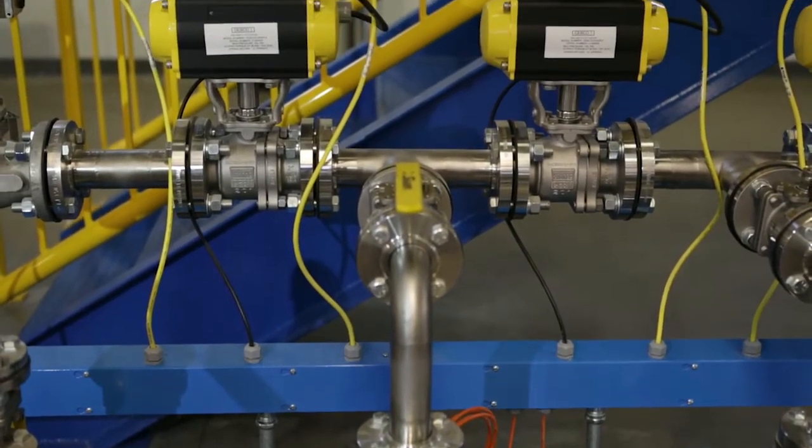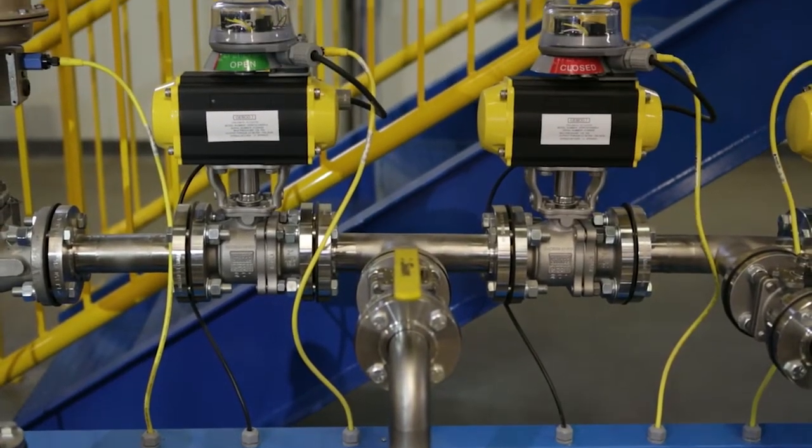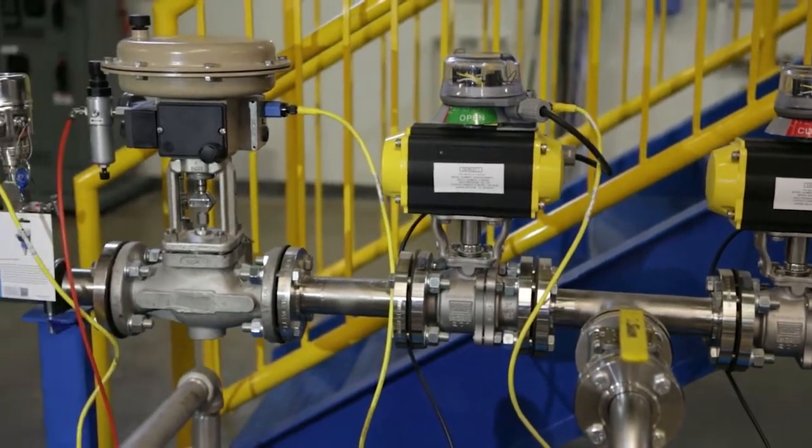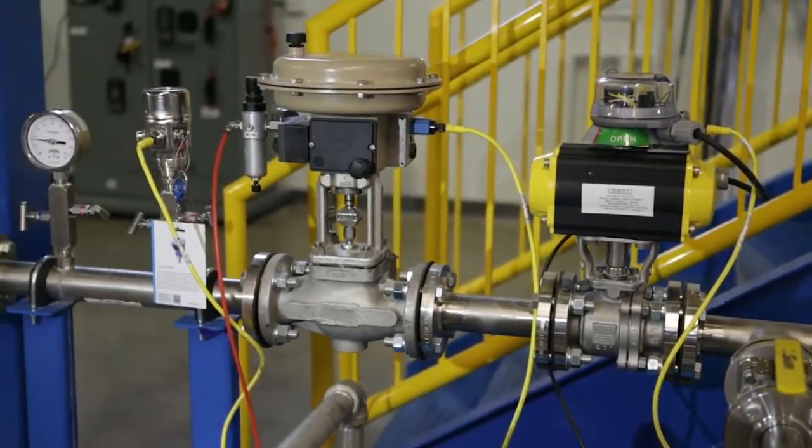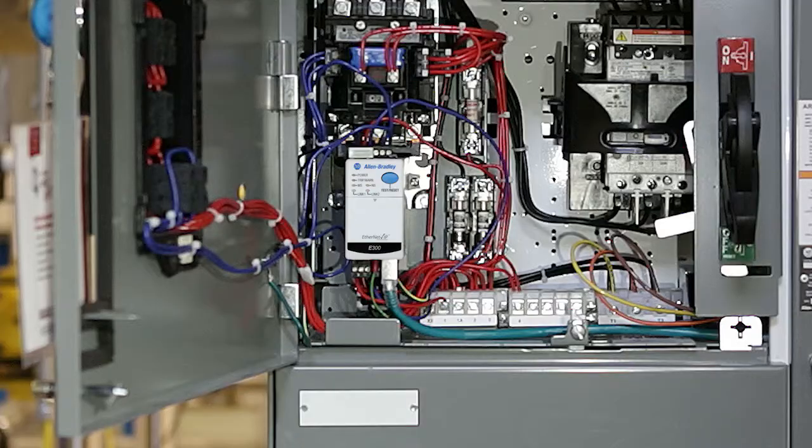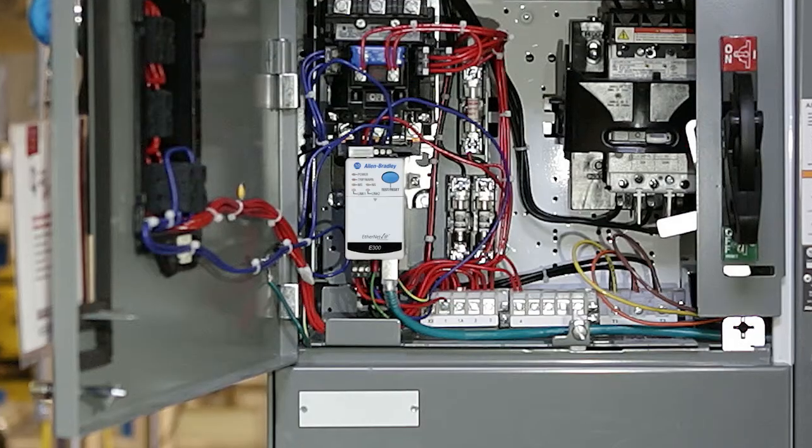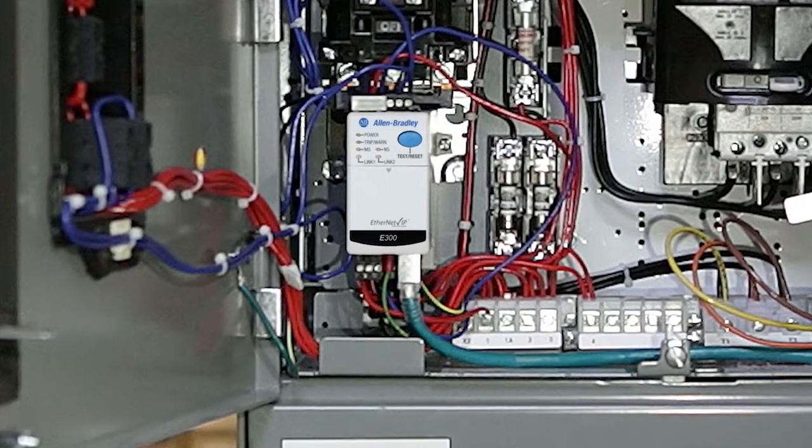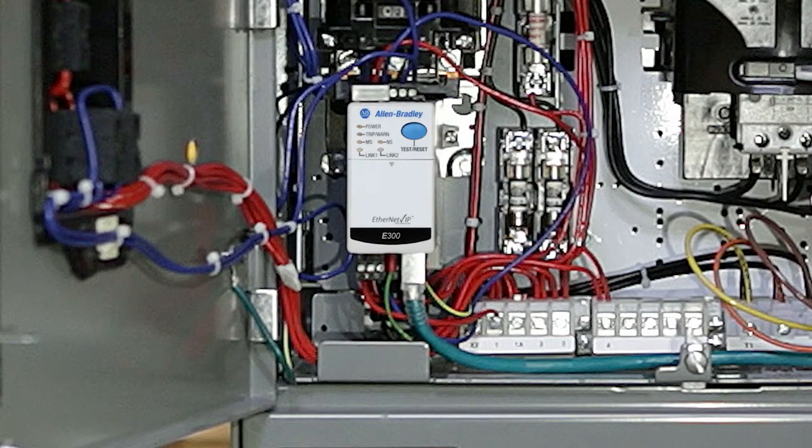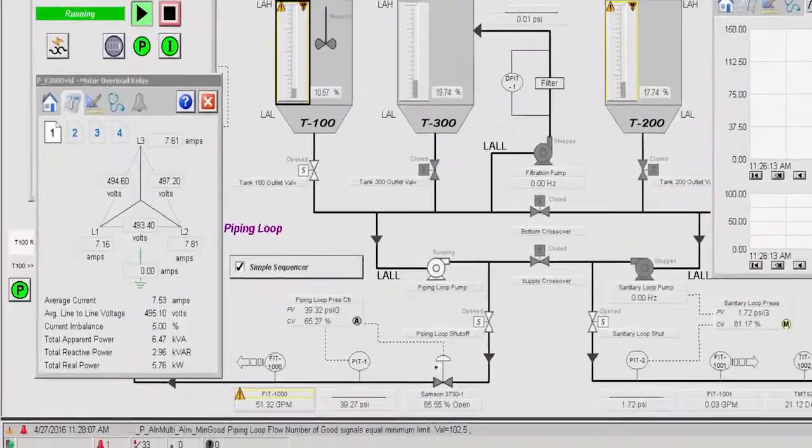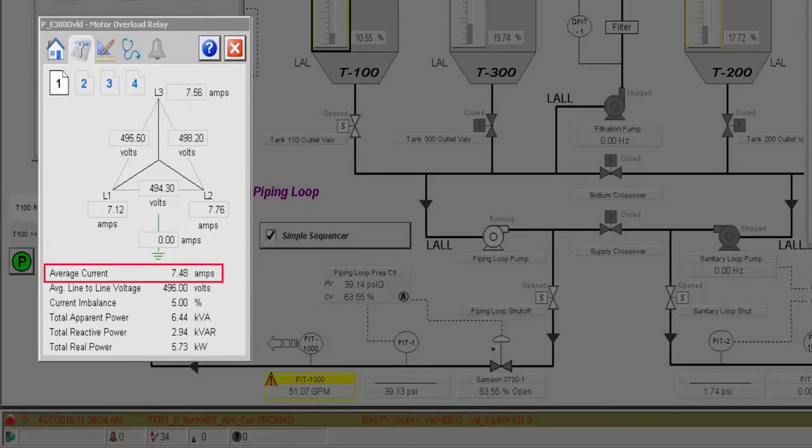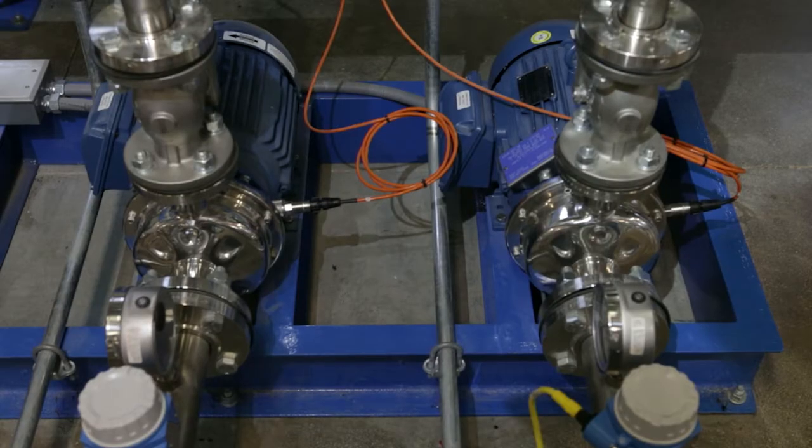Pump 1 is controlled by a conventional motor starter and downstream on the flow line is a control valve. We have installed a motor starter based on the E300 overload relay, which has a voltage and current measuring sensor that will measure actual power consumed by the motor.